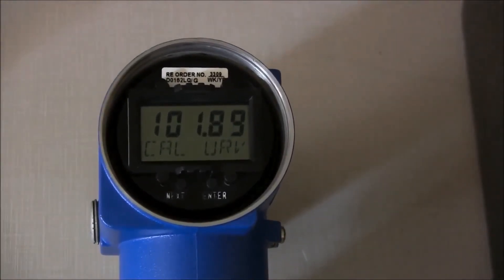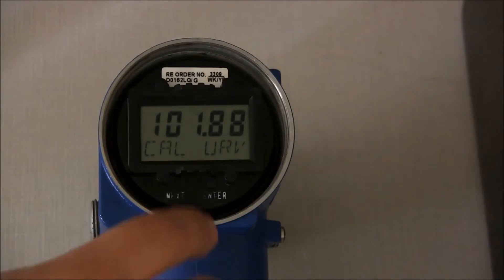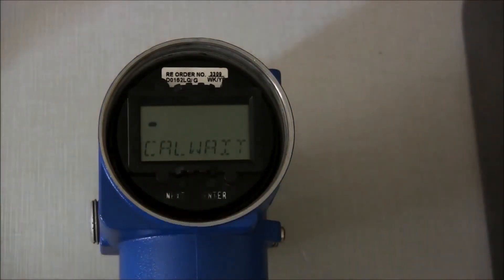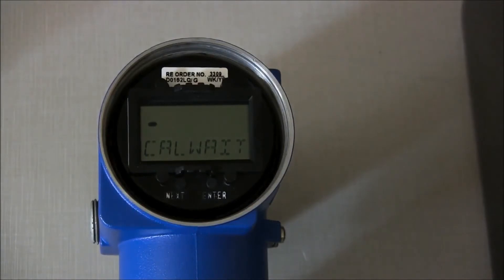Once the required pressure has been applied, press the Enter button and CalWAIT will be displayed. This may take several seconds. When CalURV has been completed, URV Done will be displayed.